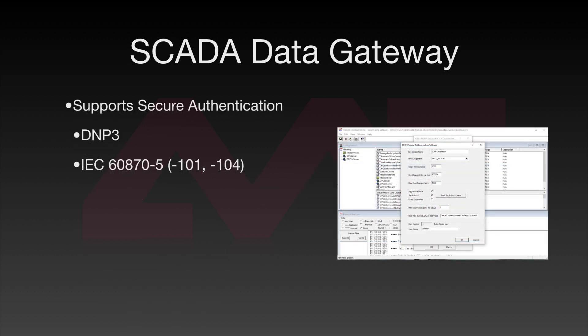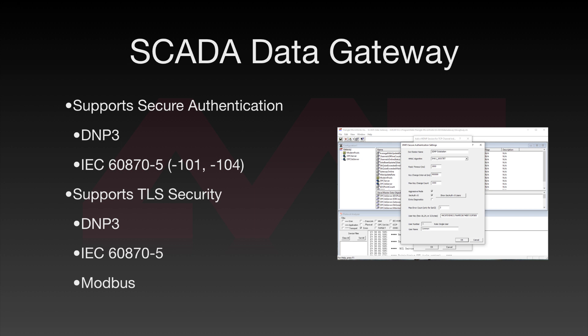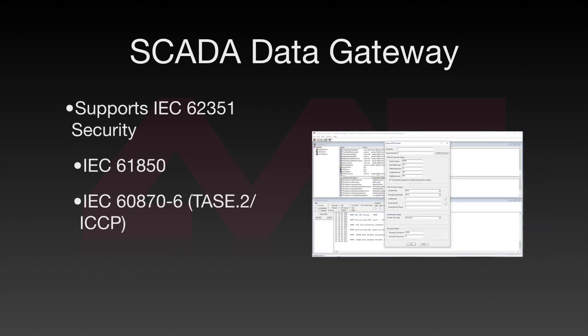The SCADA Data Gateway also supports secure authentication for DNP3 and IEC 60870-5, as well as TLS security for DNP3, IEC 60870-5, and Modbus. The SCADA Data Gateway also supports IEC 62351 security for IEC 61850 and IEC 60870-6 TASE-2 ICCP. It also supports security for OPC UA, as spelled out in the OPC UA specification.